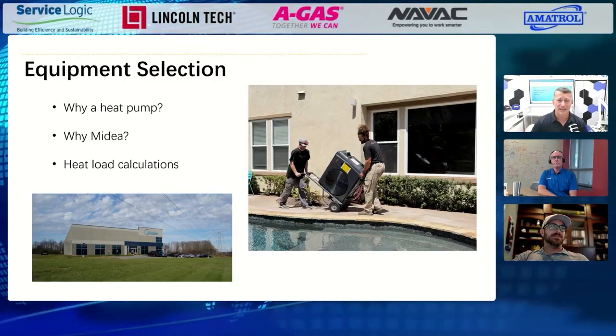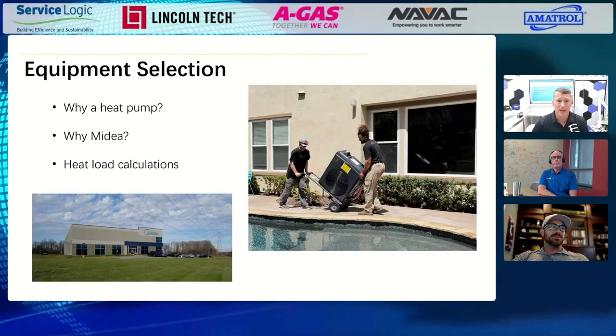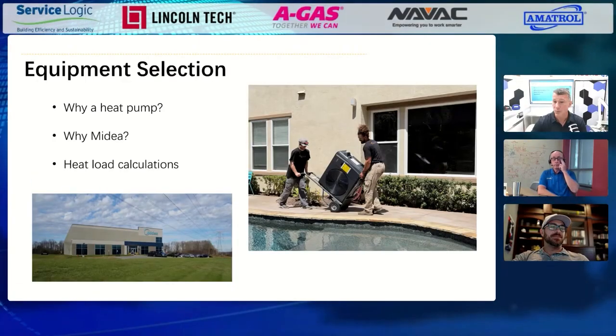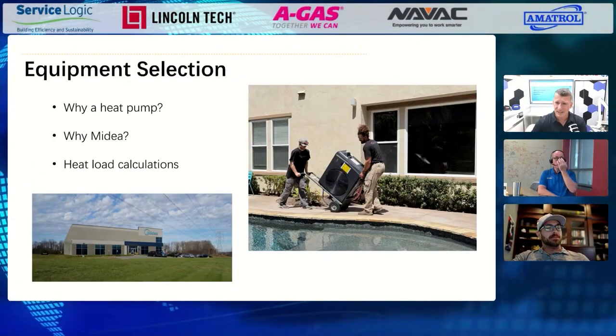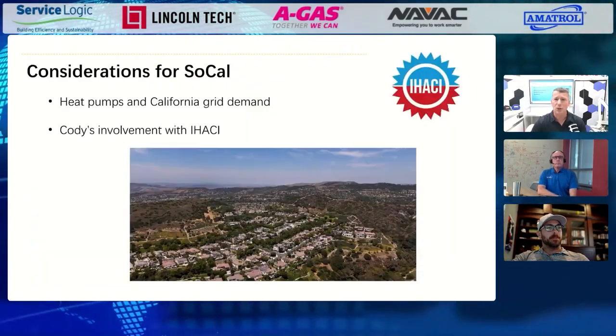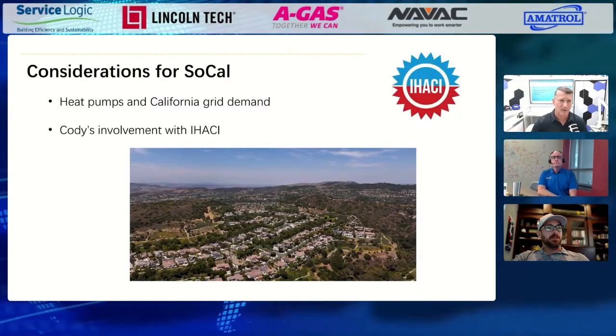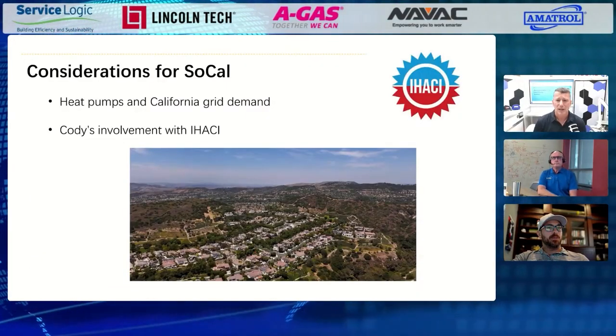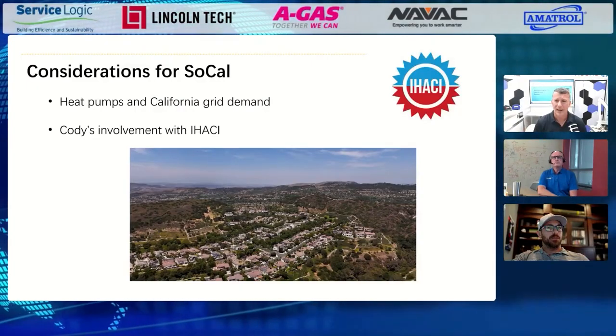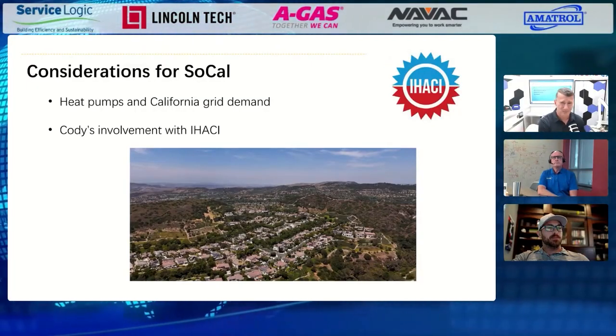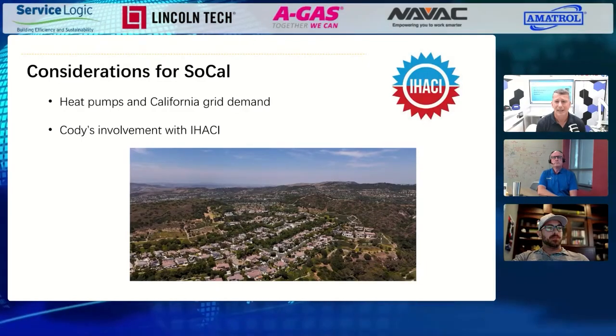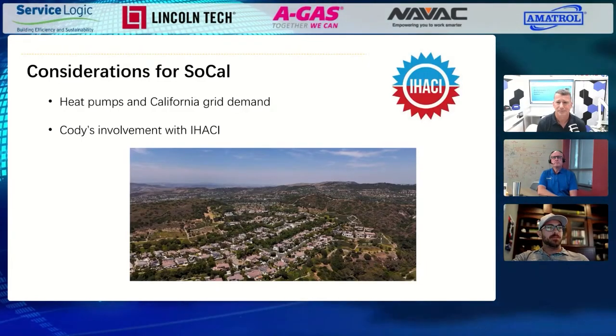So in your scenario, you're designing for cooling load, and the heating load isn't as important. In other areas, like here in the Midwest, I've been focusing on designing equipment around heat load calculations, because with our inverter we have such a decent range of operation in cooling, with proper turn-down ratios. There's a lot we can do. But for you, it really comes down to having enough heat while primarily focusing on the cooling and the operation there.